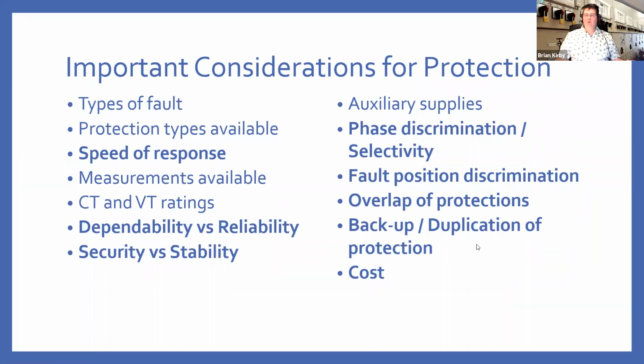In the UK, all protection runs with backup and duplication schemes, so that your backup will be another form of protection to your primary form, and your duplication will be the same form of protection, but usually by another vendor to give you that common failure mode protection. And then cost, obviously, as we've mentioned.